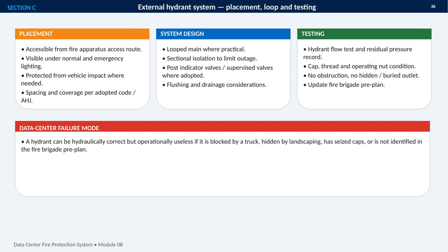This section focuses on the external hydrant system, with attention to placement, loop design, and testing. A hydrant needs to be reachable from the fire apparatus access route and clearly visible in both normal and emergency lighting. Where vehicle impact is possible, protection may be necessary, and spacing must provide the coverage required by the adopted code and the authority having jurisdiction.